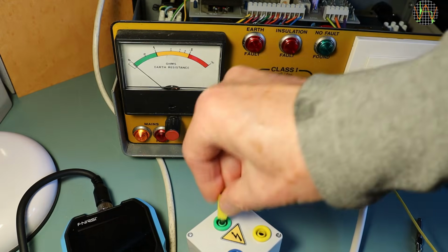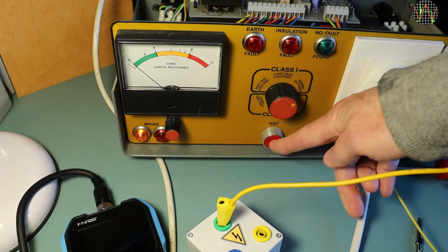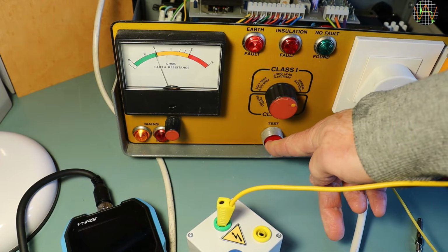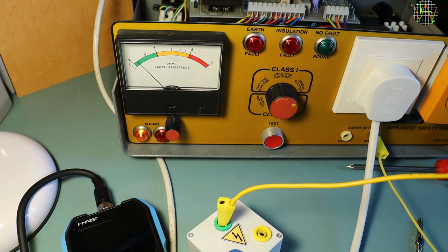What's the alternative? I don't have any resistors suitable for these tests, but instead of a resistor and my super low resistance earth return wire, I can replace both with a much longer and thinner return wire instead. That wire distributes the heat if I only do very short tests with pauses in between. Using a trial and error approach, I found a return lead that brings the result pretty much exactly to 0.1 ohm.